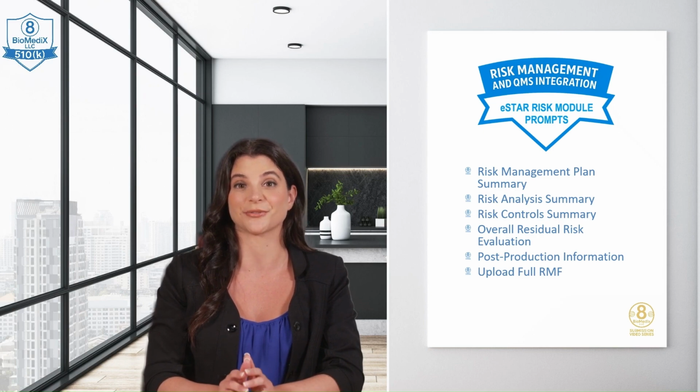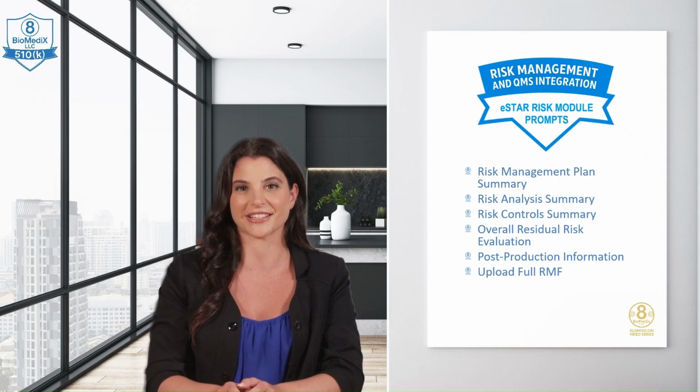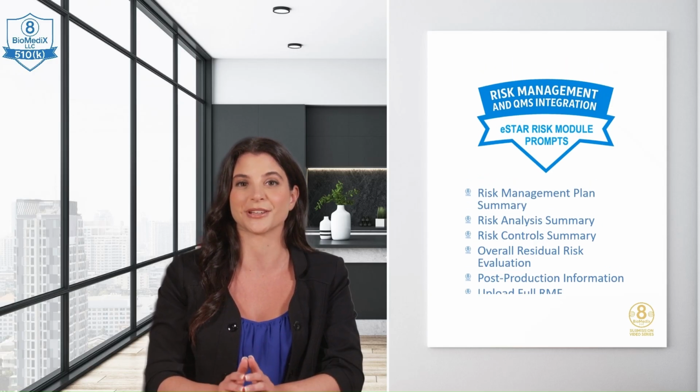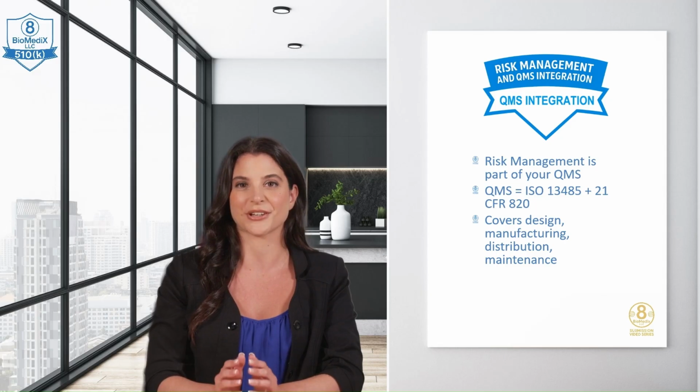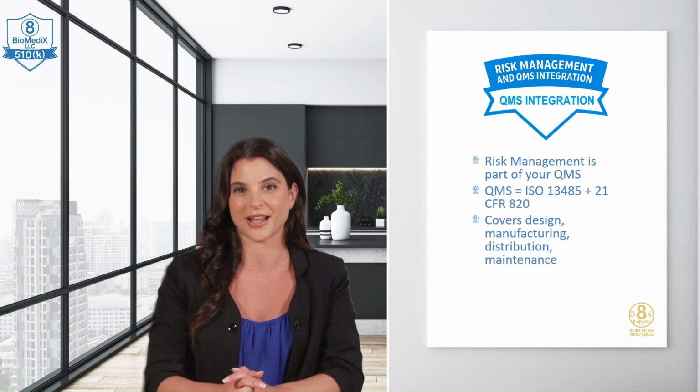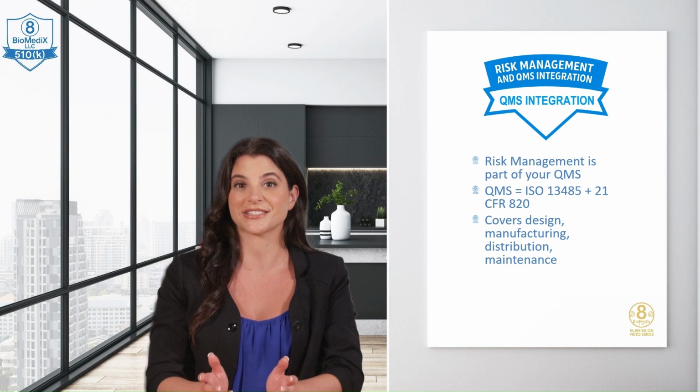Quality management system, QMS, integration. Your risk management activities are an integral part of your company's broader QMS. The QMS governs how your device is designed, manufactured, distributed, and maintained. For medical devices, the primary standards are ISO 13485 and the FDA's Quality System Regulation, 21 CFR Part 820. eSTAR does not contain your QMS, but it demands evidence of its effectiveness.